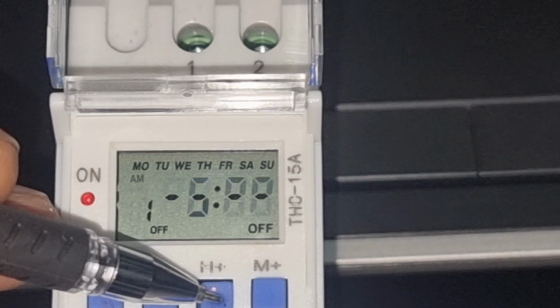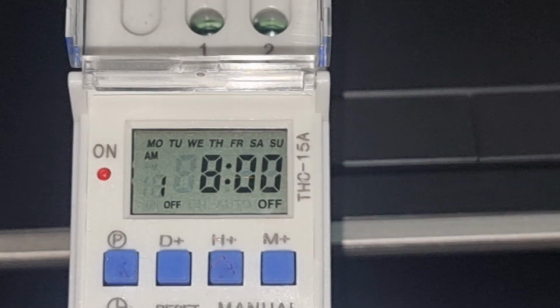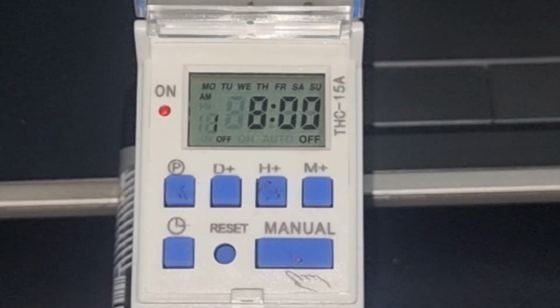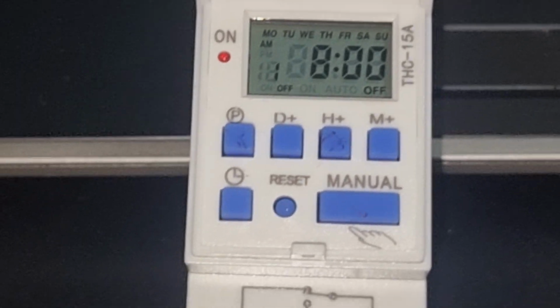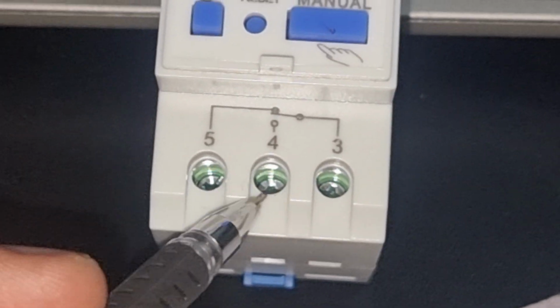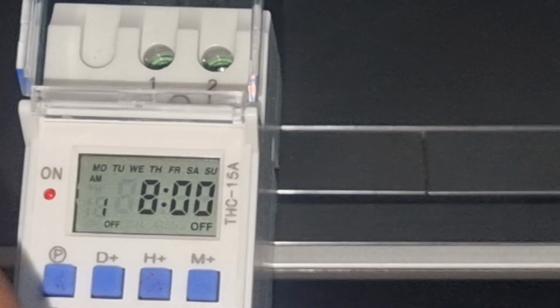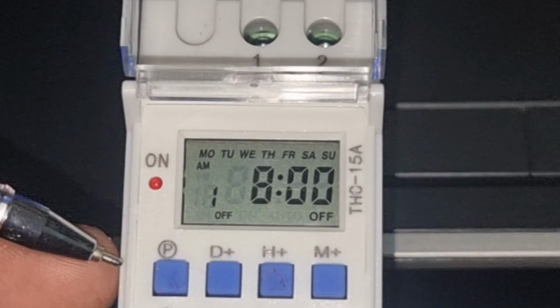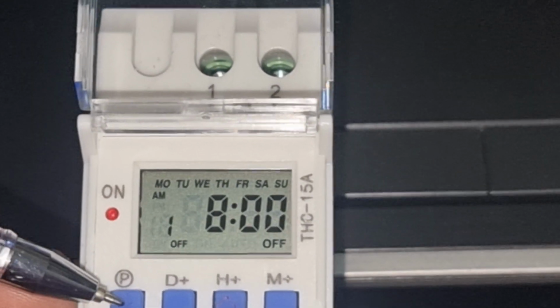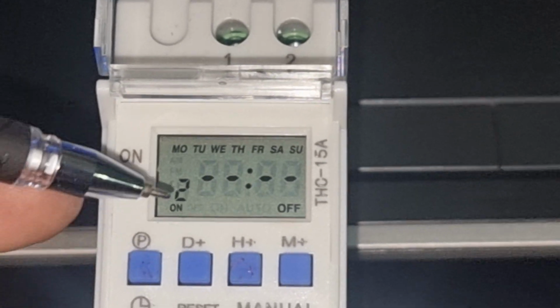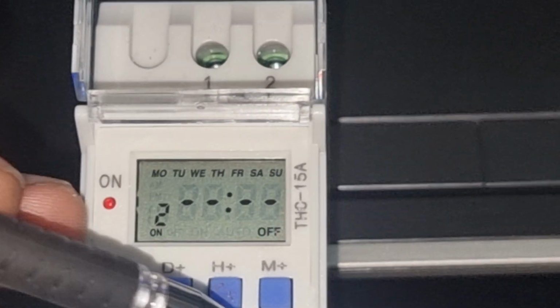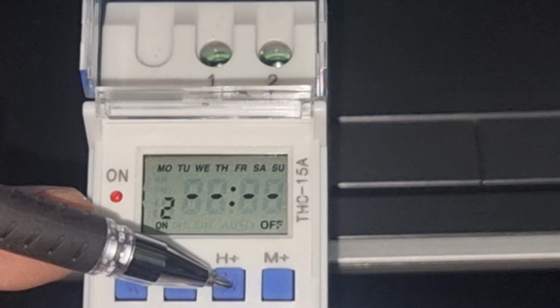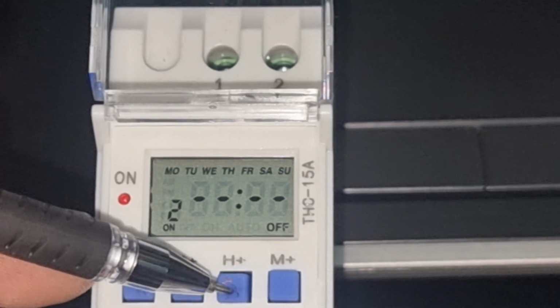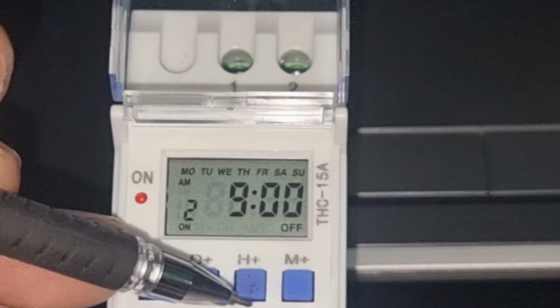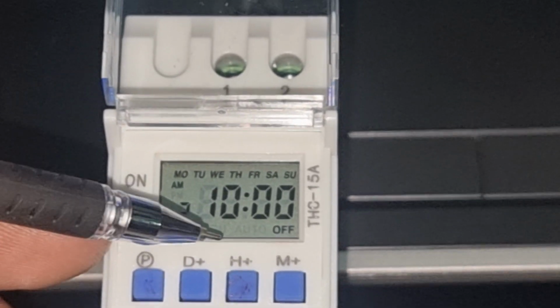Then I press H, this one I want to be 8. So at 8 it will turn off. Meaning if 6 is on and 8 is off, pump number 1 we will use on point number 4, pump number 1 is running. Then next we need the second pump to run for 2 hours, so we press P again. Here is time number 2 on. Before we gave 2 hours on, now we give 2 hours off. So 8, 9 and 10, at 10 it will go on.